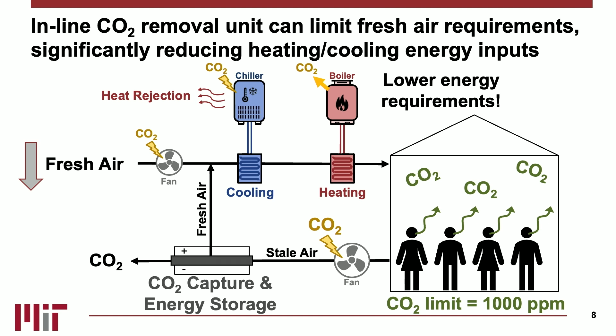Now, we can focus on the impact that this may have by looking at a large office building consisting of 1,000 occupants. They breathe CO2 out at a rate of 40 grams per hour, and we need an airflow of 40,000 cubic meters per hour in order to maintain the CO2 concentrations below 1,000 ppm.